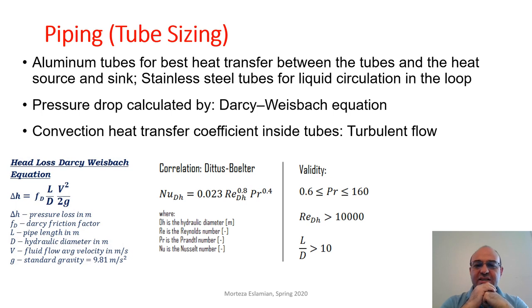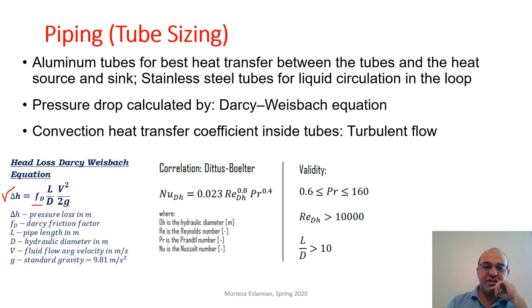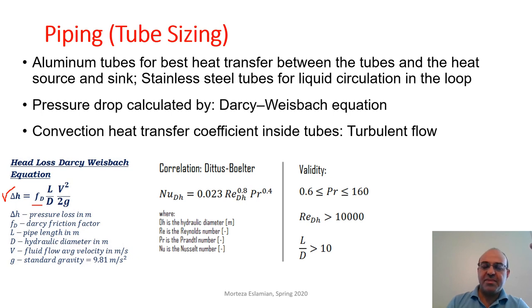Pressure drop is calculated using the Darcy-Weisbach equation. The friction head loss delta H in a horizontal pipe is: H = f * (L/D) * (V²/2g), where L is tube length, D is tube diameter, V is fluid velocity, and f is the friction coefficient obtained from the Moody chart. For forced convection heat transfer in the turbulent region, the Dittus-Boelter correlation is used to find the Nusselt number and therefore the convection heat transfer coefficient, valid for Reynolds number based on hydraulic diameter greater than 10,000.